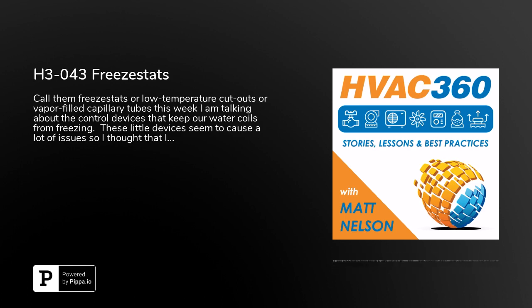If you have an automatic reset, that can be bad because, again, you're talking temperature here. If the unit trips off and there's an automatic reset, it warms up a little bit, trips off again, warms up a little bit, trips off again, and you could still have a potential to freeze out a coil. So I'm always in favor of the manual reset. Obviously, there are some conditions where you're going to get away from that, but by default, I would just have a manual reset. So, now the exciting part, and this is where I dig deeper. I'm like, okay, you say 12 to 18 inches and the unit trips.